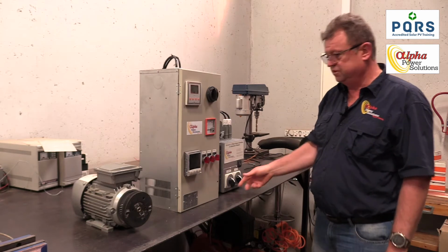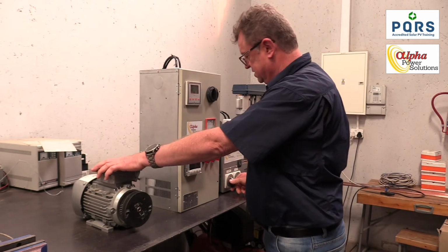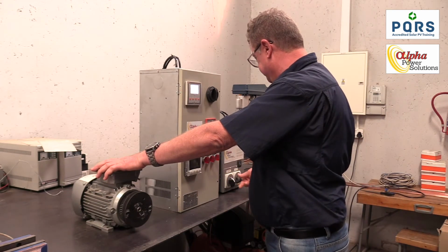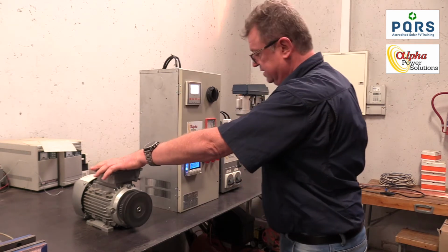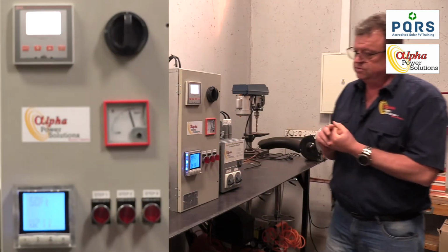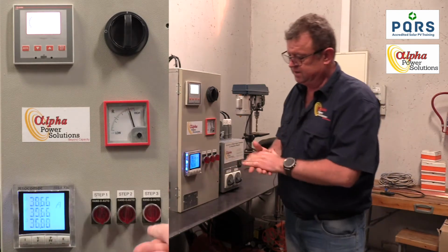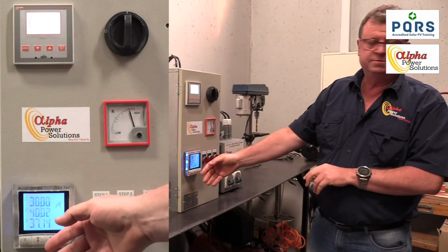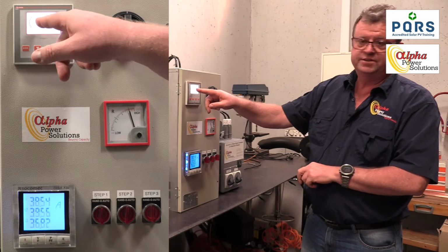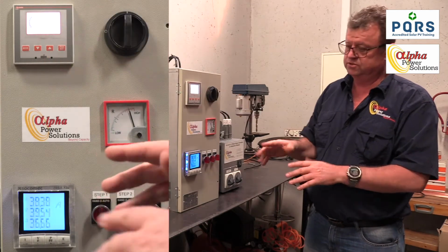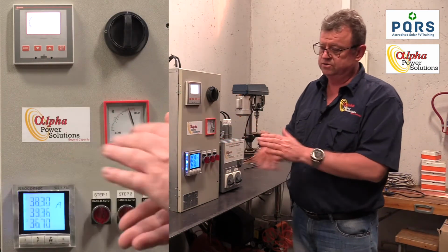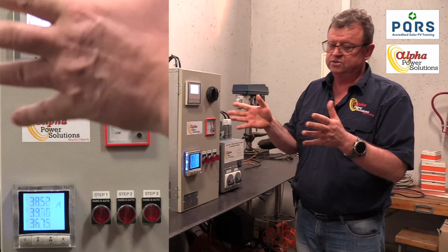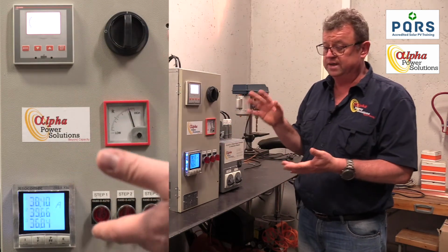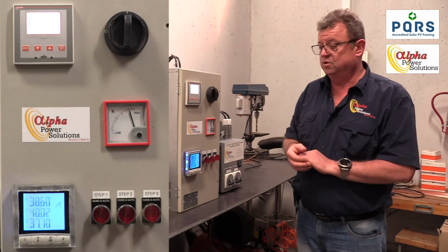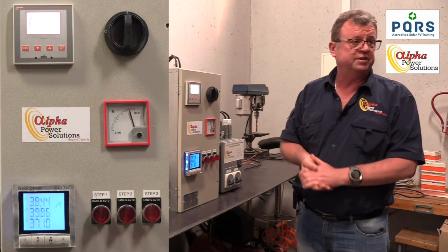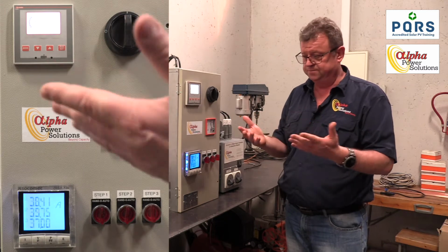So what I want to do first is start the motor and get things going. So basically the motor is now spinning, as you can see. There's some current being drawn, and the power factor is extremely poor because right now there's no connected load to the motor. So the vast majority of the power being consumed by the motor is for the magnetic field that the motor needs in order to spin.